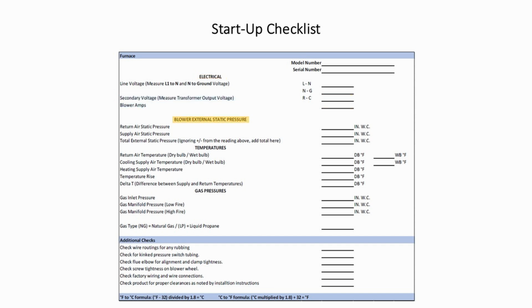Under blower static pressure, using a manometer or magnehelic, read the return air static pressure. Enter here in inches of water column. Supply air static pressure. Enter here in inches of water column. Total external static pressure, ignoring the positive and the negative from the reading above, add the totals together. Under temperatures, for return air temperature, record the dry bulb and the wet bulb temperatures. Under cooling supply air temperature, record the dry bulb and the wet bulb temperature.